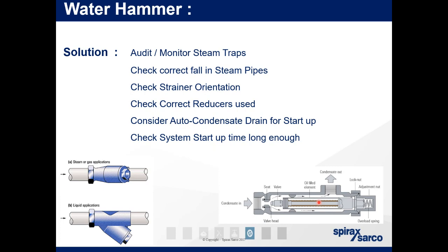Again, lack of separators. So if you have wet steam from, say, carryover from your boiler, and incorrect drainage or not enough drainage, we recommend as a point on main line drainage, you should have a trap set every 30 to 50 meters to maintain dry steam. So if you don't have enough traps, you'll end up with wet steam and therefore the potential for water hammer. Did that answer that question? I think there were 2 parts to that, was there? That was basically if there are specific scenarios or conditions that increase the likelihood of water hammer occurring. Yeah, so again, like we were saying, bad insulation, trap failures, lack of separators, those kind of things.